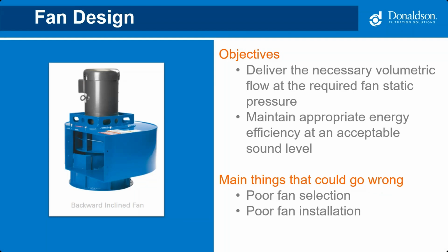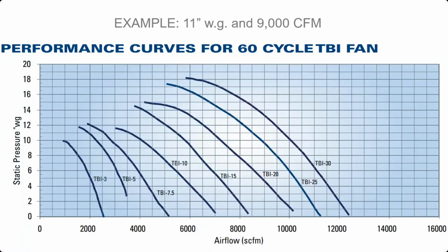For example, non-material handling fans located on the clean side of a collector are more efficient than material handling fans on the dirty side of the collector. Fan challenges generally fall into two categories: poor fan selection and poor fan installation. Fans are sized based on the system total static pressure and the required airflow. For example, let's say that I need to size the fan for the example I gave you earlier, 11 inches, and the airflow was 9,000 CFM.